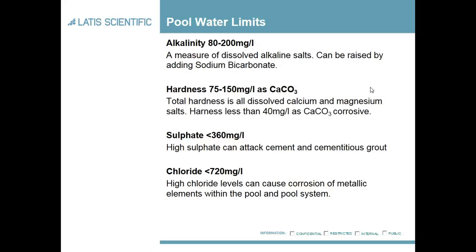The hardness is all of the calcium and magnesium salts. It's particularly relevant because low hardness leads to corrosivity, whereas at very high levels it behaves more like high alkalinity. Sulfate level — ideally you want lower than 360 milligrams per litre. It can be quite high depending on the constituents of the incoming water from the mains supply.